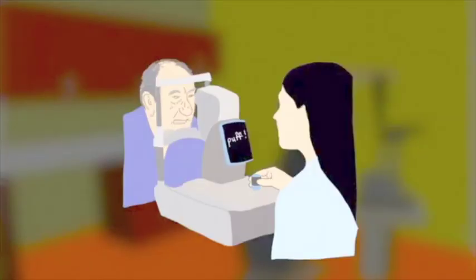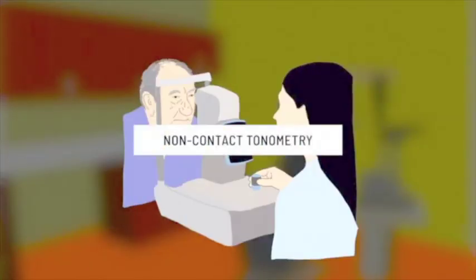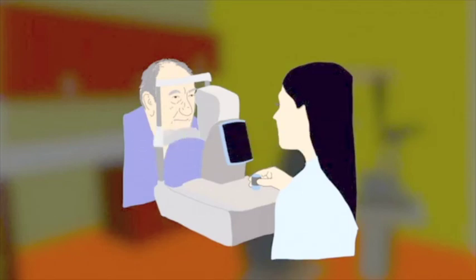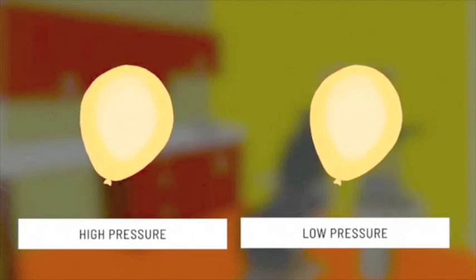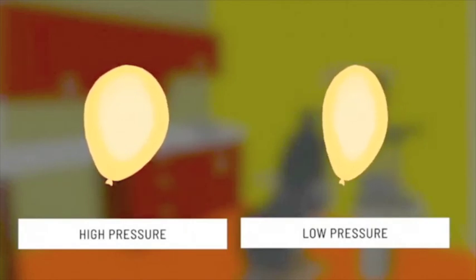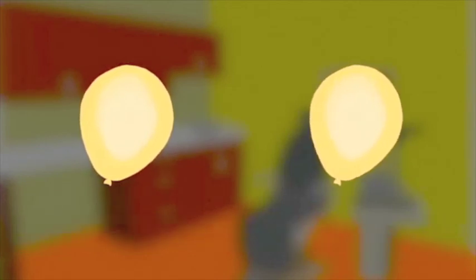The air puff test, or more correctly non-contact tonometry, works by shooting concentrated air into the cornea, and the machine observes how the cornea rebounds from this puff. If the eye has a low pressure, then the cornea will flatten quite a lot. But in an eye with high pressure, it will not flatten as much. Think of it like inflating a balloon. The more pressure there is inside, the harder it is to press onto it. It is this difference in rigidity that allows us to measure the pressure in the eye.